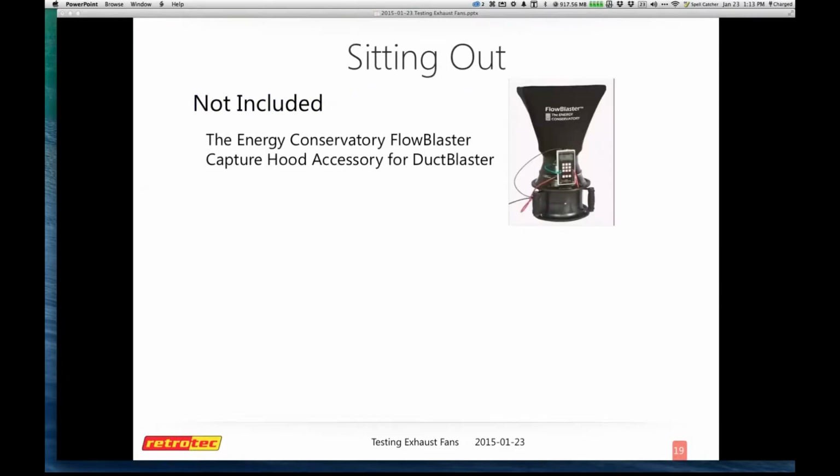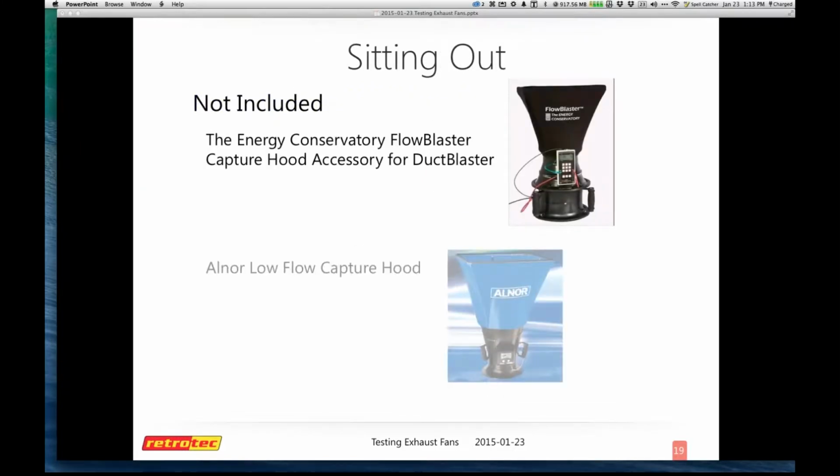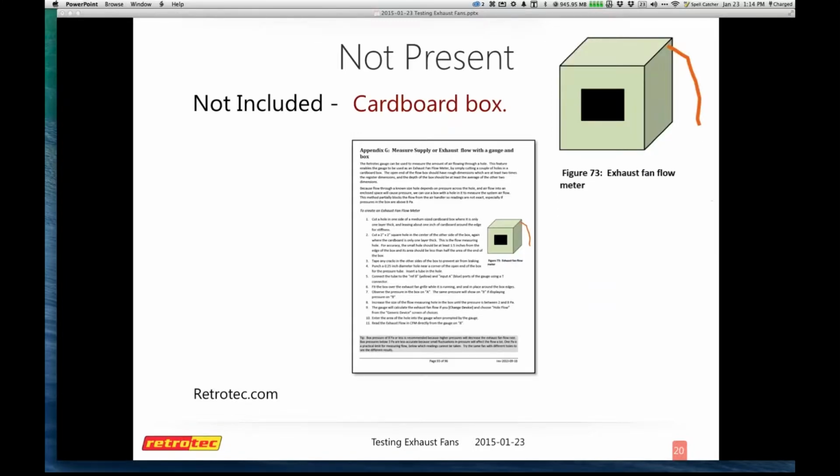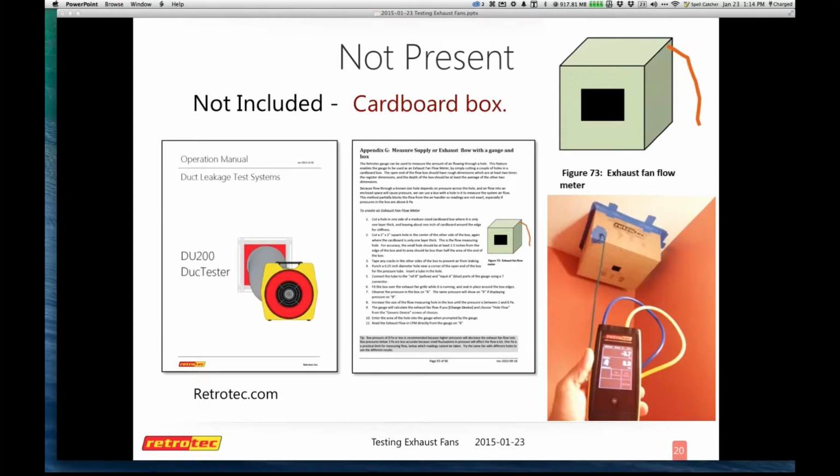But you can actually build your own exhaust flow meter device. This can measure exhaust fans. This can measure kitchen exhaust fans. And where this is incredibly valuable is if you have the really large commercial-type kitchen exhaust fans, the ones that are 600, 800, 1200 or more CFM. If you're not careful, you can lose your gauge, and small children should not be near those types of fans.